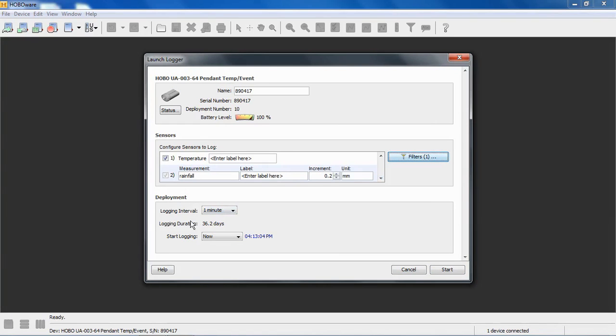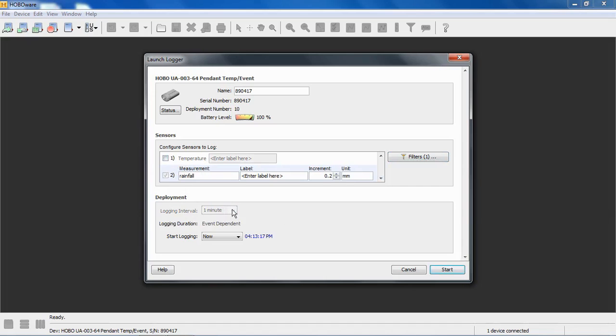We do have a logging interval available because we have the temperature channel selected. If we deselect this, if we're just using this as a rainfall sensor, you notice that the logging interval becomes grayed out and we can't change it. That's because the event channel on this logger is scanning for events every second. That's a preset scanning rate that cannot be changed.